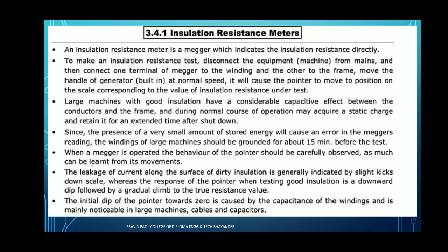Next, insulation resistance meters. An insulation resistance meter is the megger which indicates the insulation resistance directly. To take an insulation resistance test, disconnect the equipment, such as the machine, from the main switch and then connect one terminal of the megger to the winding and the other to the frame. Move the handle of the megger at the normal speed.